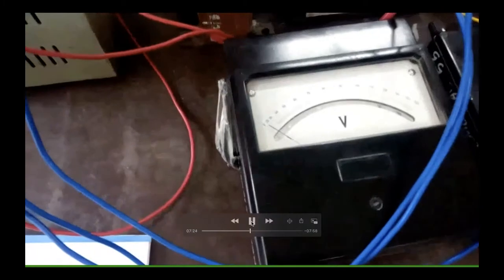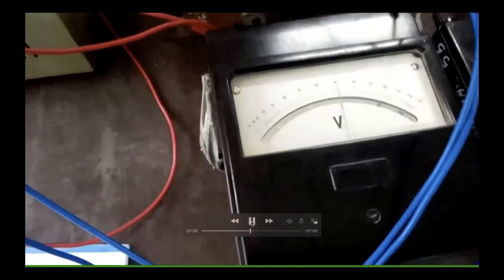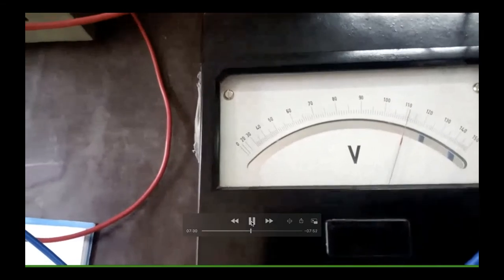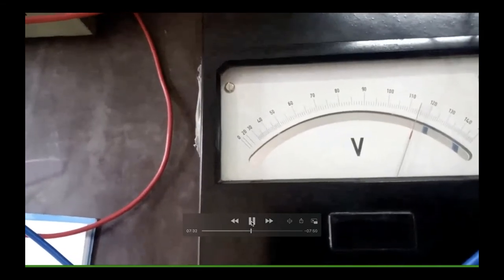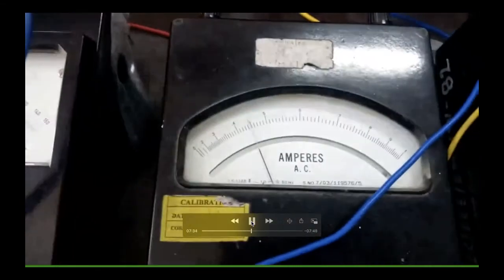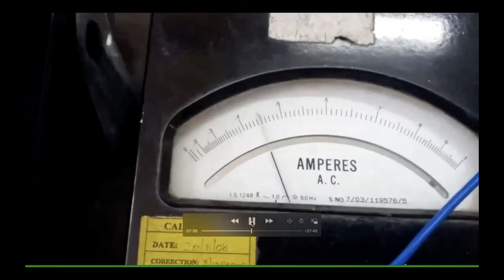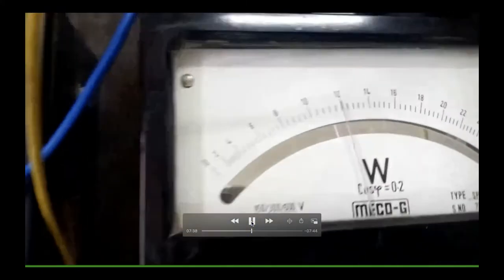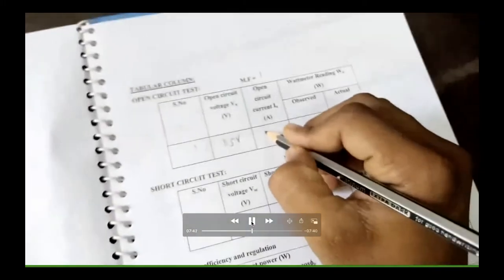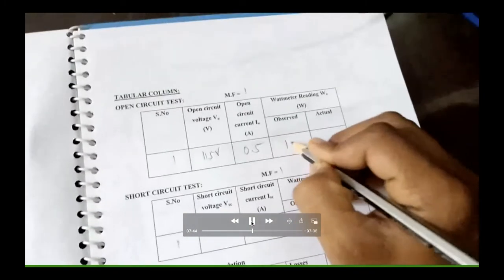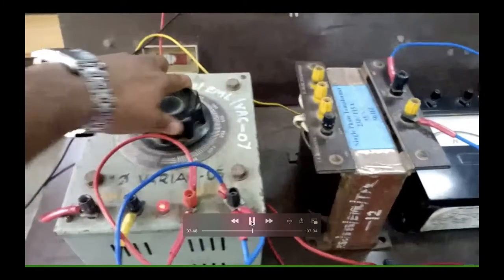So turn on the AC supply, and check the variac. Keep 115 volts. Only one reading, and note the corresponding current. It comes around 0.4 and the corresponding wattmeter reading. So open circuit current is 0.5, and wattmeter reading is 12. Multiplication factor is 1. That's all.